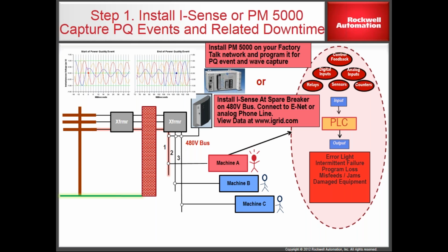That iSense monitor is a voltage-only monitor—it doesn't monitor current at all, but it's an event capture voltage monitor. So when an event comes in, you can see a capture right here at the top of the screen: the little red dot is when the event started, and this is when the event ended. The iSense will capture three cycles before the event started, the event itself however long it lasted, and then three cycles after the event ended. And it packages that data and pushes it to our server.